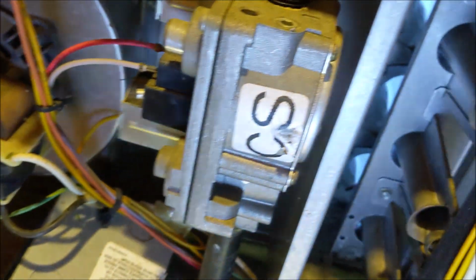Oh, here we get to see the monoport burners working. So we've got a nice, beautiful hot flame coming out. Very little discoloration, which means it's not in need of service or maintenance. These are what they call individual monoports. 1, 2, 3, 4. So this is probably going to be like 80,000. What is this? Trane, American Standard. It's the same thing, American Standard. But yeah, the gas furnace is on. Looks pretty clean.